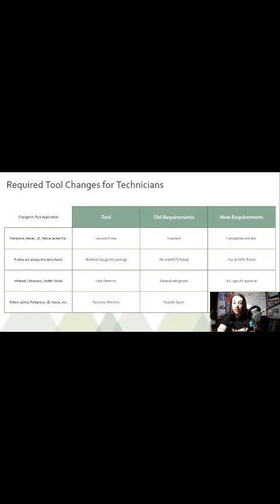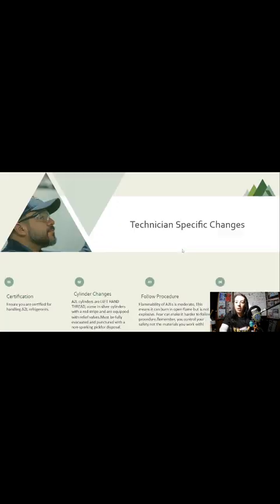Recovery machines. This is important because the old requirement had a possible spark. Some of the motors start with a spark. Yellow Jacket, Field Piece, JB, NAVAC, etc. all have A2L compatible models out already. The new requirements, obviously, are A2L approval, and it has to have no spark technology.